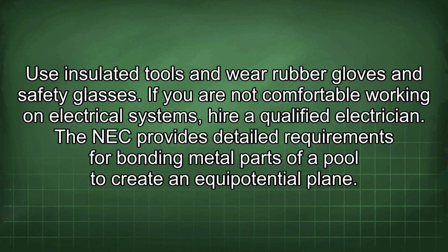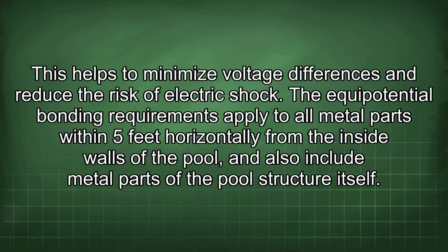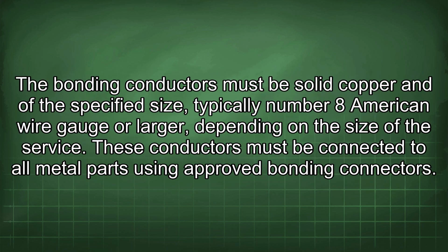The NEC provides detailed requirements for bonding metal parts of a pool to create an equipotential plane. This helps to minimize voltage differences and reduce the risk of electric shock. The equipotential bonding requirements apply to all metal parts within 5 feet horizontally from the inside walls of the pool, and also include metal parts of the pool structure itself. The bonding conductors must be solid copper and of the specified size, typically number 8 American wire gauge or larger, depending on the size of the service.